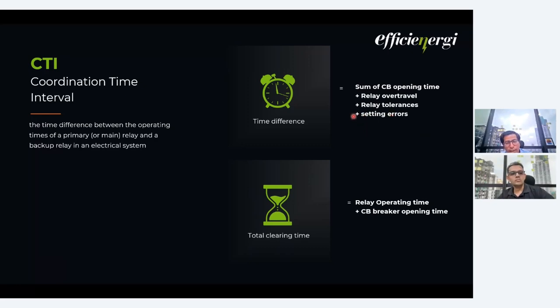So relay tolerances and setting errors, you must have an idea, because we have already explained the relay over travel. That overshoot means, suppose the fault current crosses the set value downstream, the relay goes into the operating state. Now its operating time has started, the counting has started. Let's say it has to trip at 200 milliseconds, but before that, maybe at 100 or 150 milliseconds, the fault is cleared somehow.